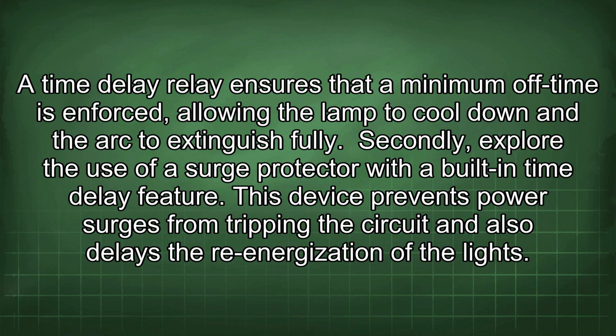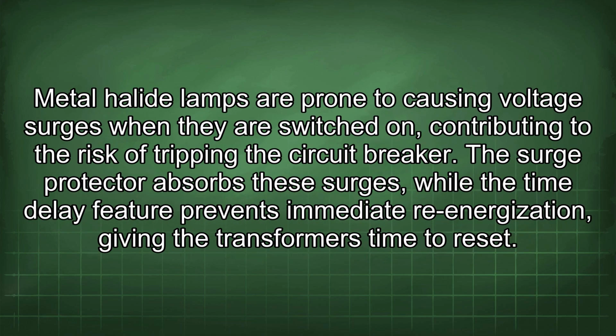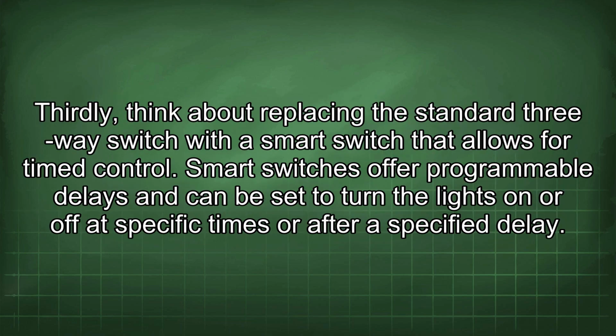This device prevents power surges from tripping the circuit and also delays the re-energization of the lights. Metal halide lamps are prone to causing voltage surges when they are switched on, contributing to the risk of tripping the circuit breaker. The surge protector absorbs these surges, while the time delay feature prevents immediate re-energization, giving the transformers time to reset. Thirdly, think about replacing the standard three-way switch with a smart switch that allows for timed control.